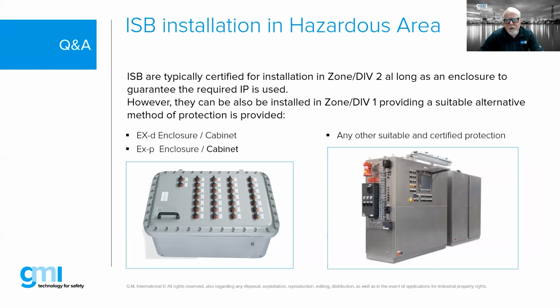This is also a solution if we have issues where the cable length is a problem for us. We're limited maybe by our cable length based upon the inductance and capacitance. So we might actually have to take the associated apparatus barriers and install them closer to the field device in order to make sure that the loop falls under the entity loop parameters.